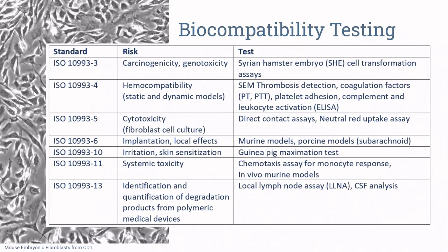For our glutamate sensor to be approved by the FDA, it must undergo rigorous testing to meet the ISO 10993 standards for biomedical evaluation in medical devices. As our device is designed to be permanently implanted and in contact with blood, although indirectly via the cerebrospinal fluid, these tests run the gamut, as you can see from this table. Of particular interest is our device's biocompatibility in the highly collagenous environment of the subarachnoid space. We want to ensure minimal interference with the normal trabecular architecture and the flow of CSF. This would be achieved using neutral red assays and fibroblast cell cultures to determine the cytotoxicity of our materials.